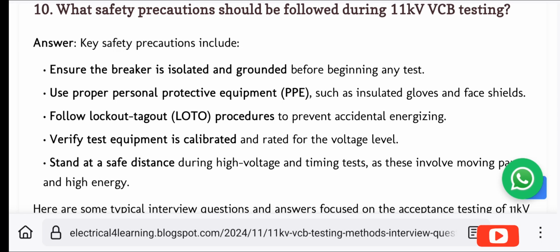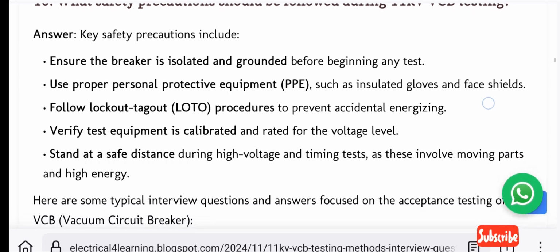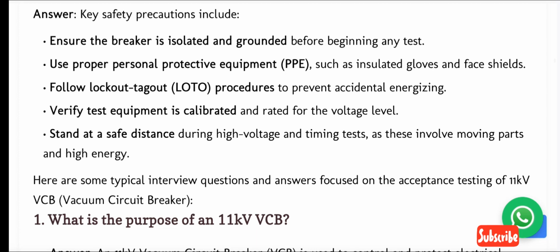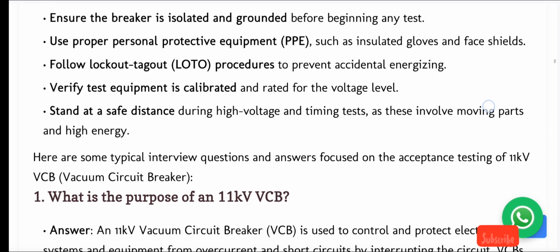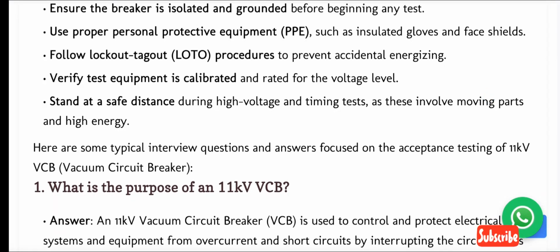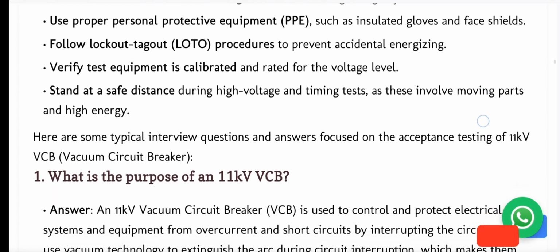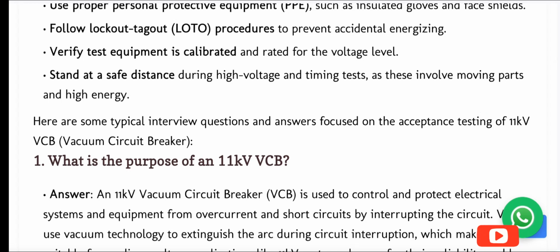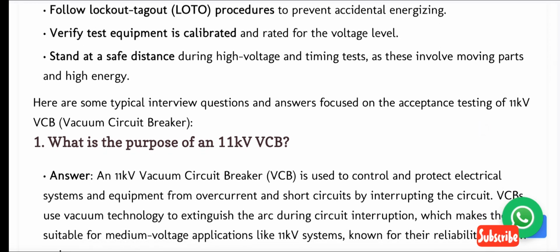Answer. Key safety precautions include: ensure the breaker is isolated and grounded before beginning any test. Use proper personal protective equipment (PPE) such as insulated gloves and face shields. Follow lockout-tagout (LOTO) procedures to prevent accidental energizing. Verify test equipment is calibrated and rated for the voltage level. Stand at a safe distance during high voltage and timing tests, as these involve moving parts and high energy.